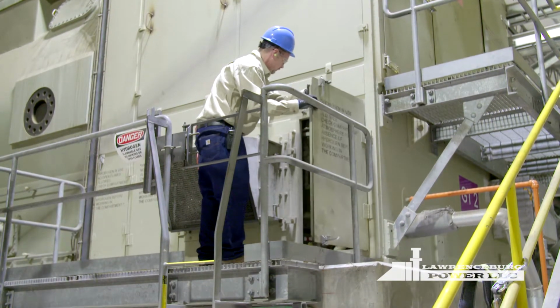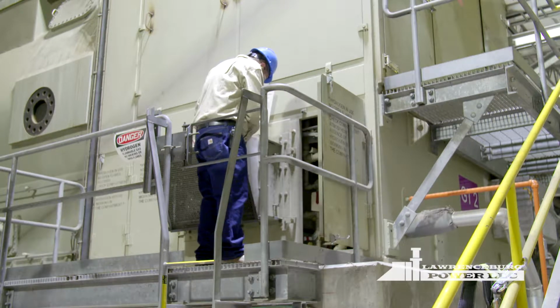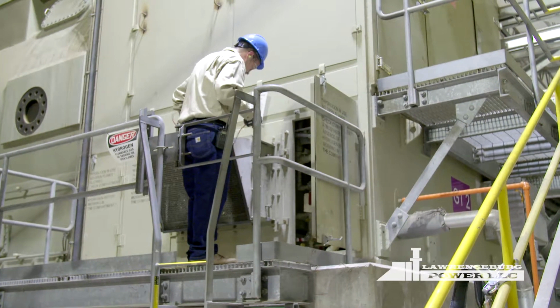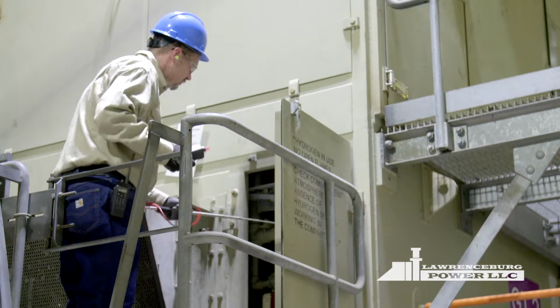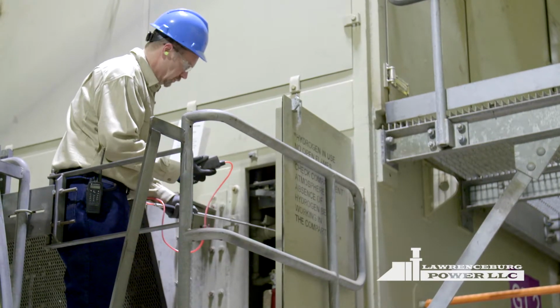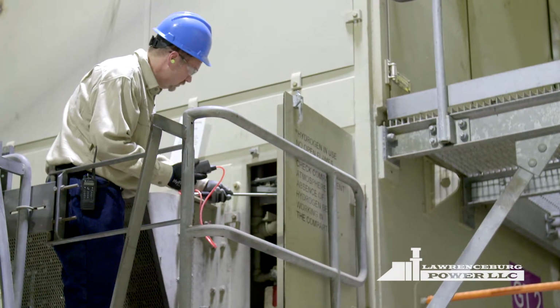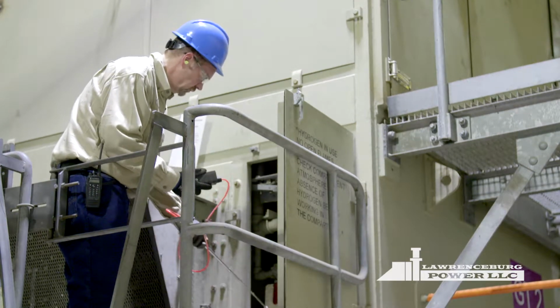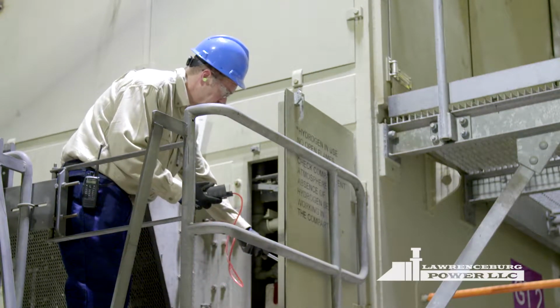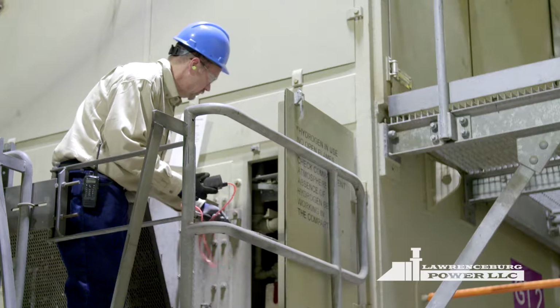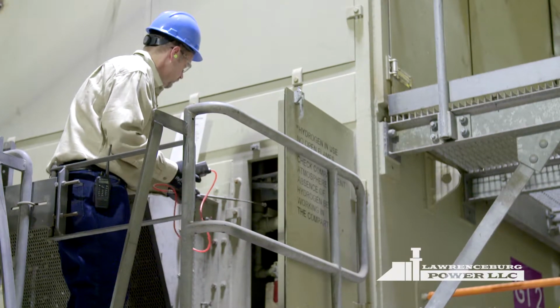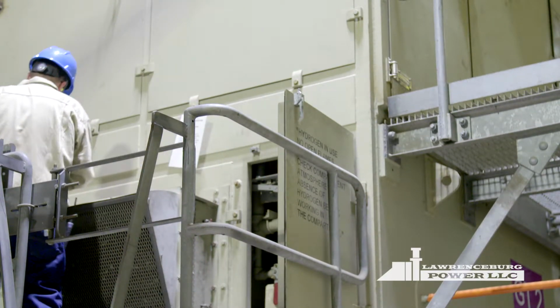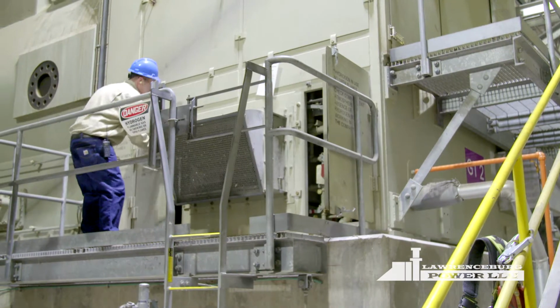The range of flammable mixture for hydrogen gas is between 4% by volume, the lower explosive limit, to 74% by volume, the upper explosive limit. The lower explosive limit describes the leanest mixture of gas and air that will burn, and the upper explosive limit describes the richest flammable mixture. Natural gas and hydrogen levels above the upper explosive limit will not ignite but are still very dangerous.